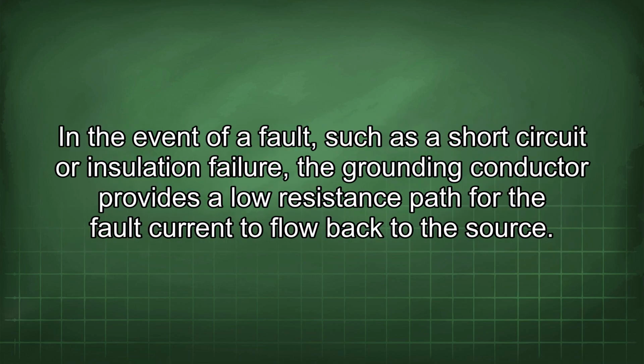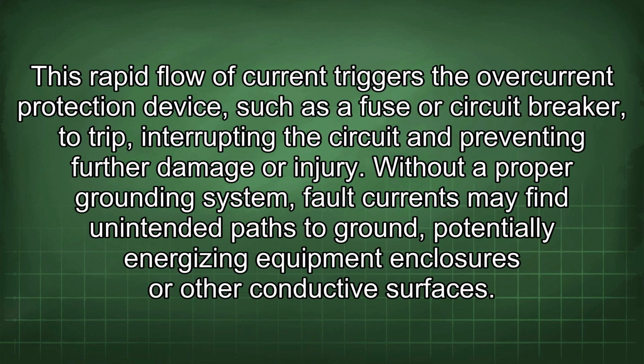In the event of a fault, such as a short circuit or insulation failure, the grounding conductor provides a low resistance path for the fault current to flow back to the source. This rapid flow of current triggers the overcurrent protection device, such as a fuse or circuit breaker, to trip, interrupting the circuit and preventing further damage or injury.